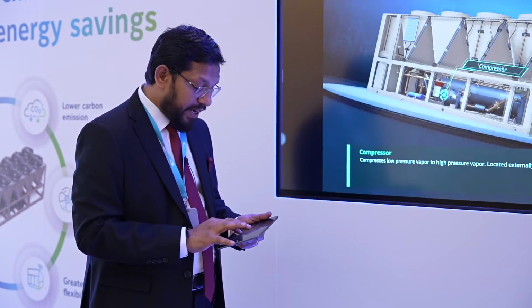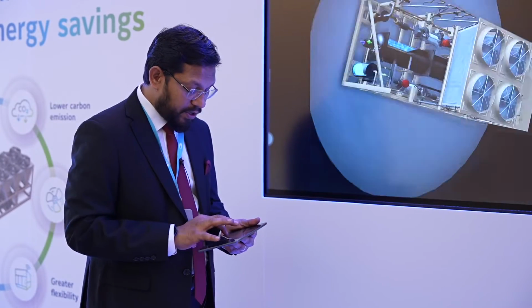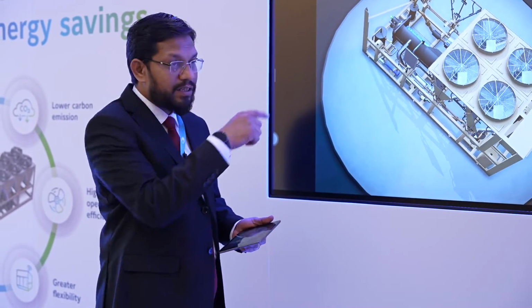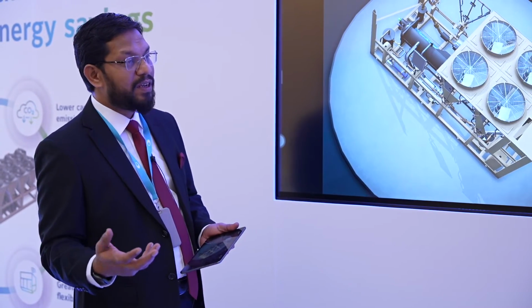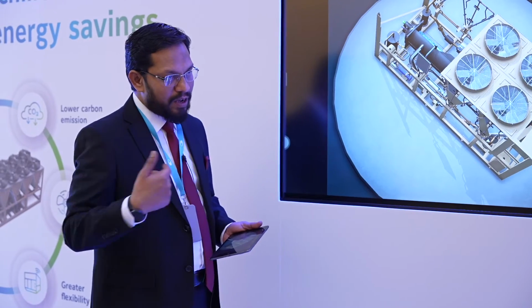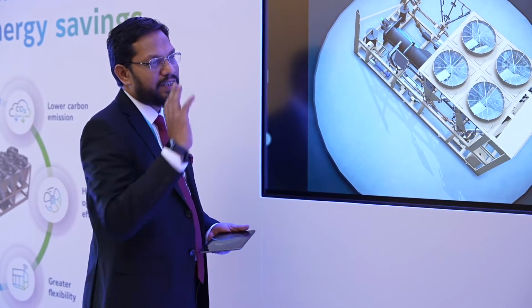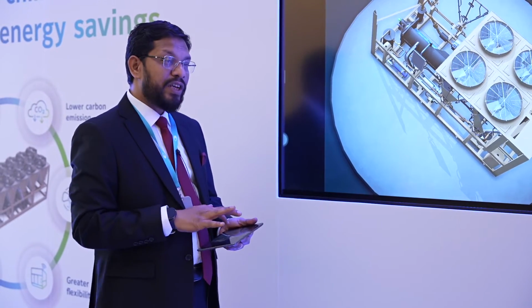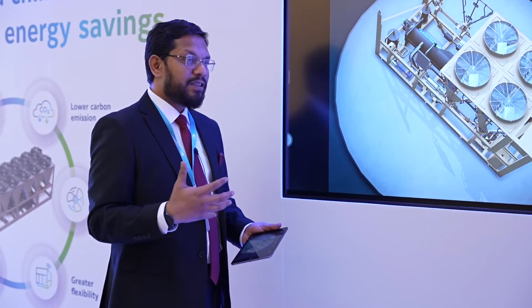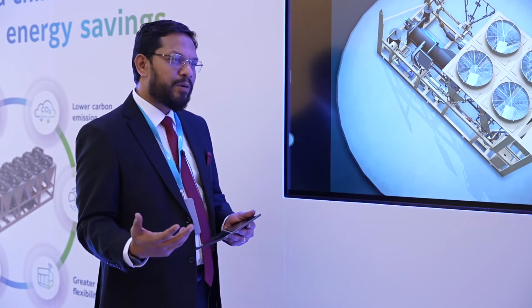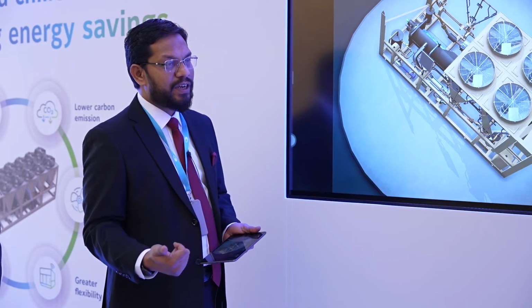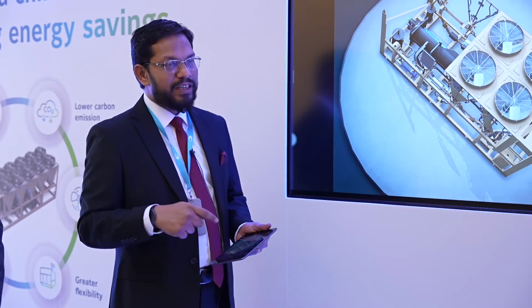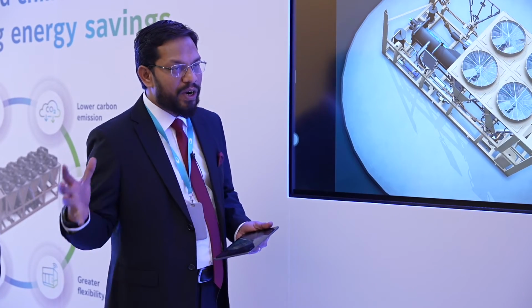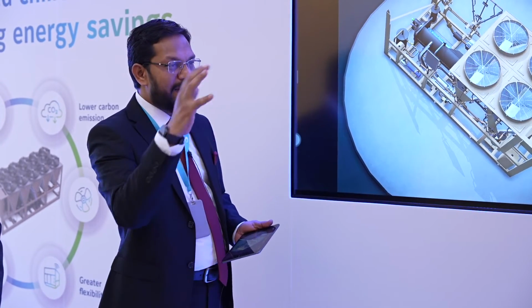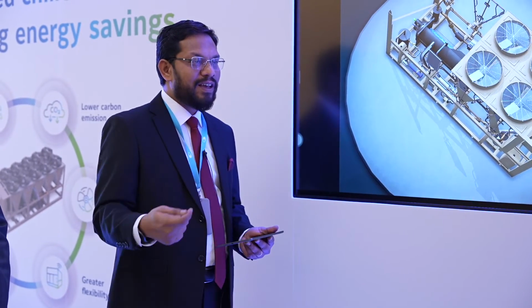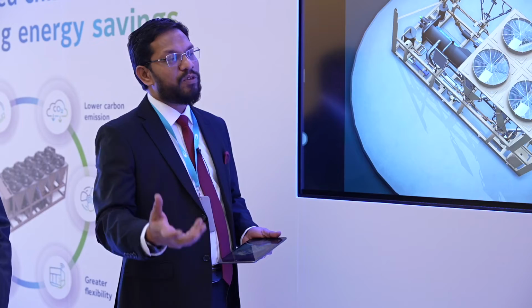These machines also come with an evaporator. If you see the cross section of these chillers, you will see the evaporators here, the black shells, which transfer the heat from your medium, the chilled water coming from the building load, to the refrigerant, where the heat is then transferred back to the atmosphere. Typically, chillers used to have a DX type evaporator. DX type evaporators have an issue in that they are less efficient. When the water is in the shell itself, over the years the water forms scaling inside the shell. There is no way to clean that scaling. The only way is to remove the evaporator completely.